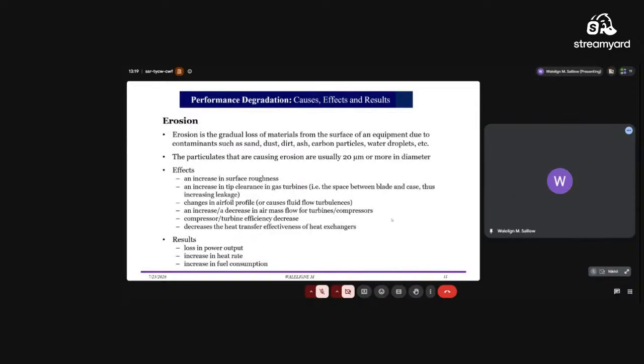The second type of physical fault that happens in a gas turbine is erosion. It's a gradual loss of material from the surface. So it affects the surface roughness, increases tip clearance, changes the aerofoil profile, and changes the air mass flow for turbine and compressor, because erosion has different effects in the compressor and turbine. In the compressor, it reduces the flow capacity, but in the turbine, it increases the flow capacity, because of the expansion on the turbine side. So the removal of material will increase the flow capacity.